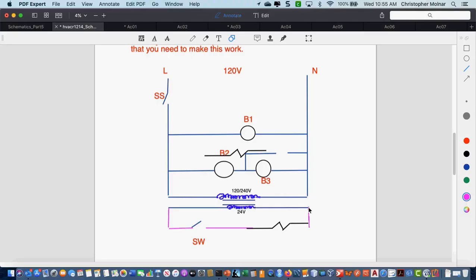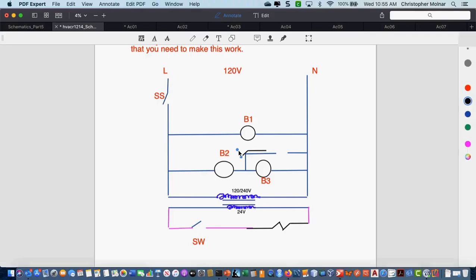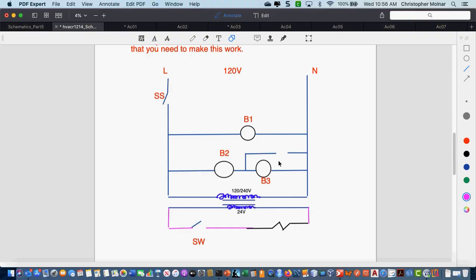Now, the other thing that I saw a couple people do, and it was actually a couple different people, let me get rid of that spare relay up there. Don't know how that happened. They connected my relay coil back to neutral. Why doesn't that work? Because it needs to be 24 volts, not 120. We never want to cross the 24-volt side with the 120-volt side. You've got to be very, very careful about that because you can melt down components that way.